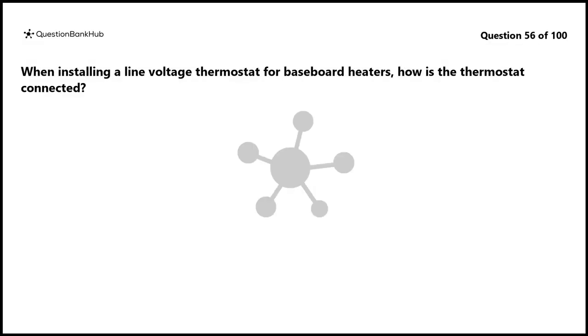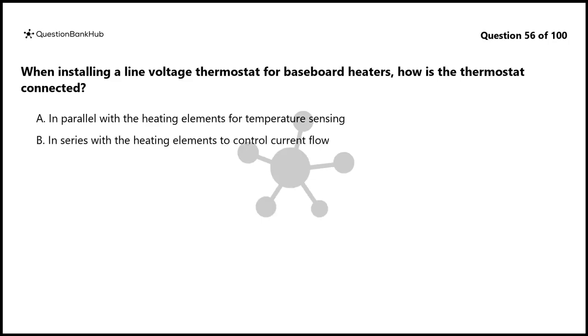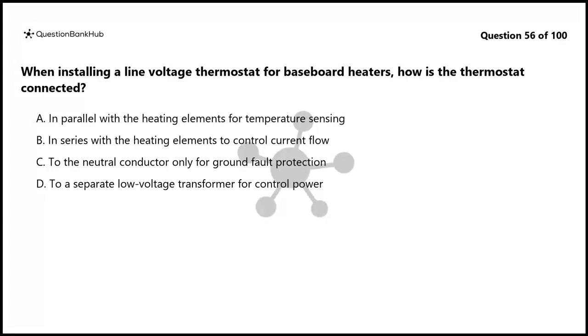Question 56. When installing a line voltage thermostat for baseboard heaters, how is the thermostat connected? A. In parallel with the heating elements for temperature sensing. B. In series with the heating elements to control current flow. C. To the neutral conductor only for ground fault protection. D. To a separate low voltage transformer for control power.